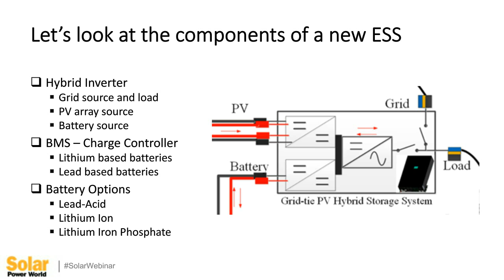So your hybrid inverter, breaking it down a little bit further, is typically a string inverter. So when I say that, I mean that we're talking about how the modules are arrayed. So you've got a string of modules wired in series, building up the voltages, running somewhere in the 200 to 550 volt range for most residential systems. It supplies AC to the grid just like a string inverter does. It takes DC from the array and/or the battery. It determines where you've got the power at and what you need. It charges from the PV or the grid, and it could be both, so that it always tries to keep the battery charge level at a useful level to the best that it can.